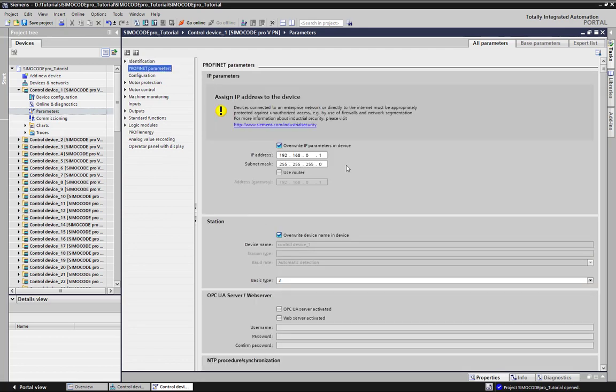If the SimoCodes will get operated in the same network, of course the IP address settings have to be changed individually for each device. Only the station name, which is also used for the Profinet device name, is individually enumerated by copy-paste.